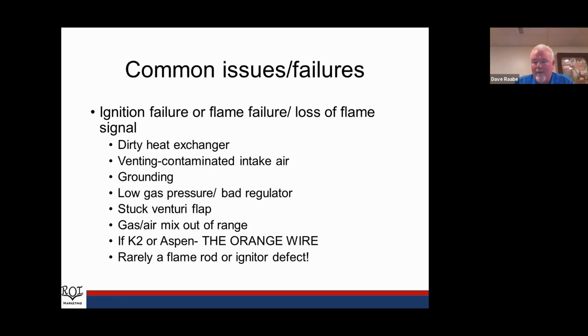We know that we need fuel, spark, and air, and we need them in the right mixture and at the right place and the right time in order to have ignition. So I guess number one is, do we have fuel? Is there fuel there? That being said, is our fan running? Do we have air? If the fan's running, we don't have an adjustment on our fan. It's always fixed at whatever speed the control tells it to run at. We do have a fuel adjustment.